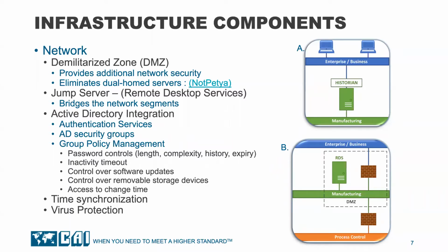Active Directory integration also allows many applications to benefit from Windows security groups. These security groups can be configured to align with functional roles such as operator, supervisor, engineer, and administrator. Active Directory integration also allows for centralized management of numerous settings such as password complexity, history, and expiry. This reduces regulatory risk. We don't have to go to individual computers to manage settings. We know that all computers are configured properly per our group policy.